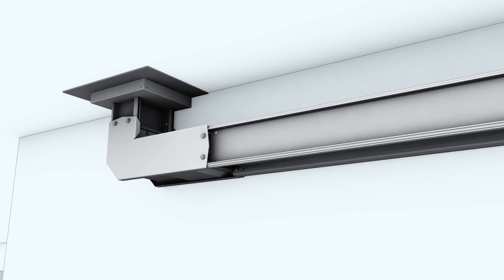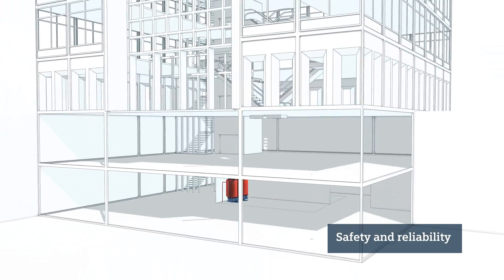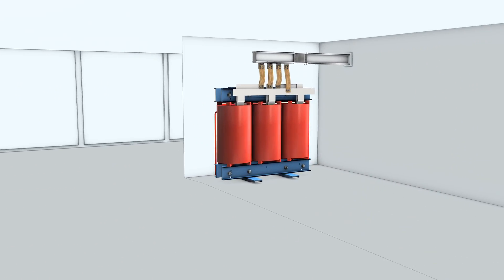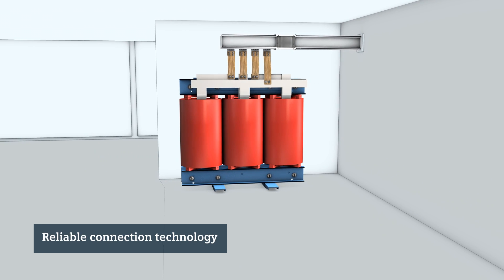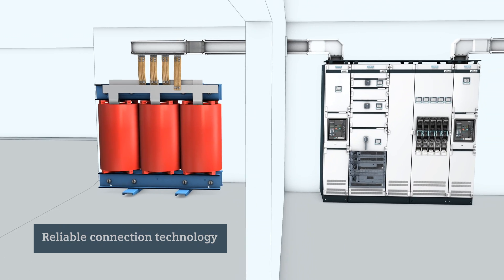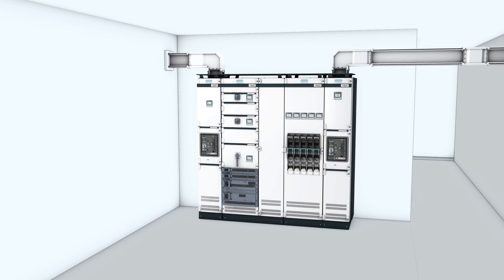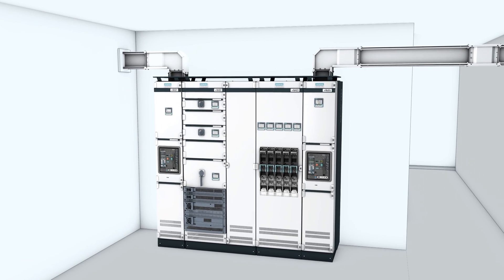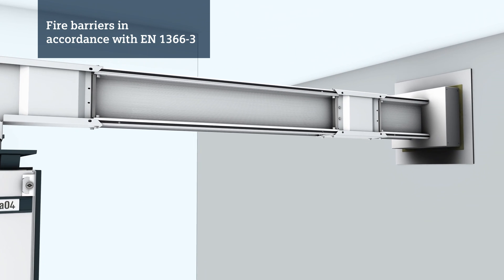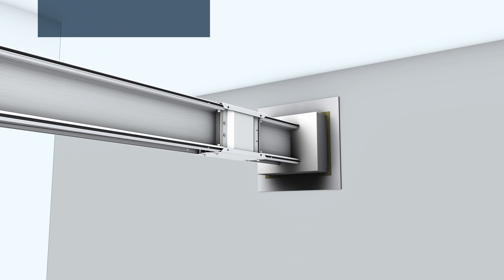When in operation, the LI system leverages its strengths, demonstrating safety and reliability in all applications. The connections for transformers and design-verified connection to the Sivacon S8 power distribution boards provide maximum plant safety. Does your installation require fire barriers? Then equip the bus bars with EI 90 or EI 120 fire barriers at critical points, and you'll meet current building safety standards.